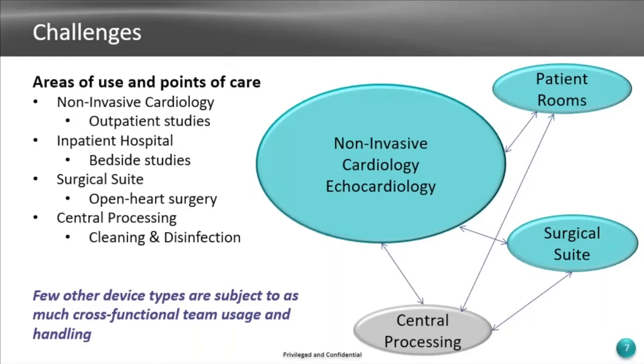To top it all off, these probes are extraordinarily delicate. It's the most delicate transducer made by any of the OEMs—the TE probe—because there's so much integration with these materials and the array. This particular array has about 5,000 elements. Just something small will destroy that array. They're that delicate.